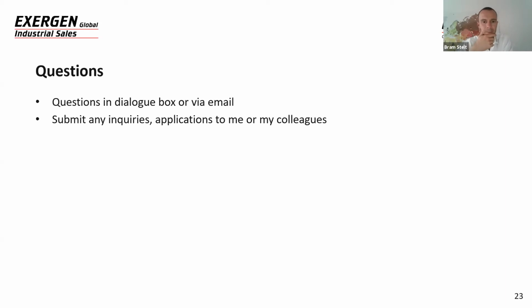Thank you. Let's go to the next question. The question is, what is the effect of ambient temperature fluctuations on the readings? It's a good one, because I explained if you have rapid or big fluctuations, it can have an effect. Our sensors are designed to compensate for ambient temperature fluctuations, and especially the heat balance. The idea is that the heat balance, that's basically why it's called a balance, is balancing various temperatures, which is tubing surface temperature, ambient temperature, and then to calculate fluid temperature. If you have big ambient temperature fluctuations, it will affect the readings.